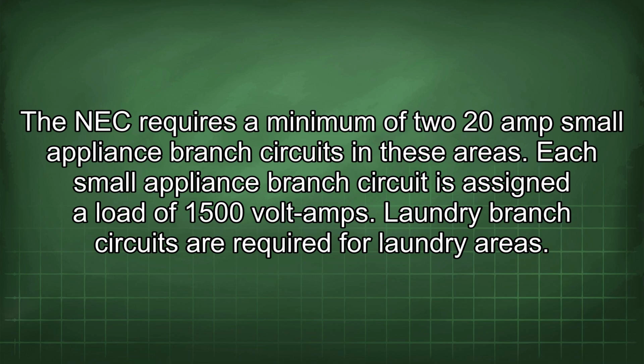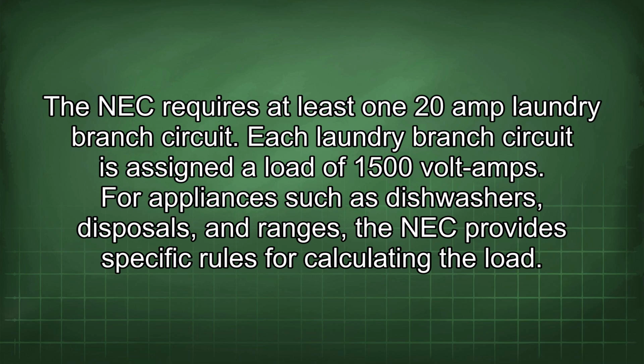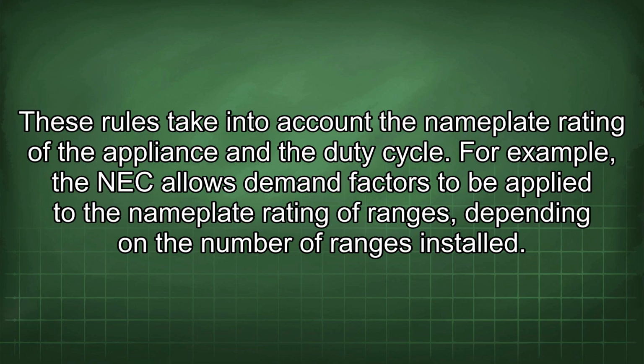Laundry branch circuits are required for laundry areas. The NEC requires at least 1 20 amp laundry branch circuit. Each laundry branch circuit is assigned a load of 1500 volt amps. For appliances such as dishwashers, disposals, and ranges, the NEC provides specific rules for calculating the load. These rules take into account the nameplate rating of the appliance and the duty cycle.